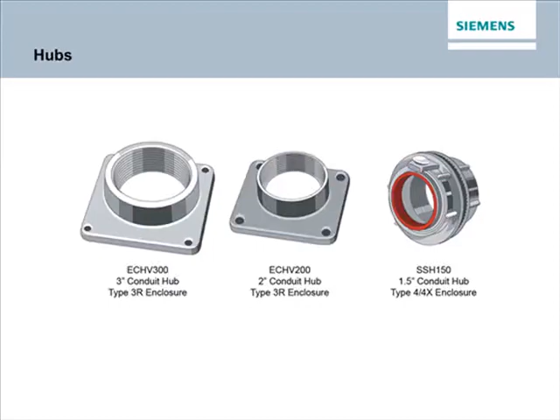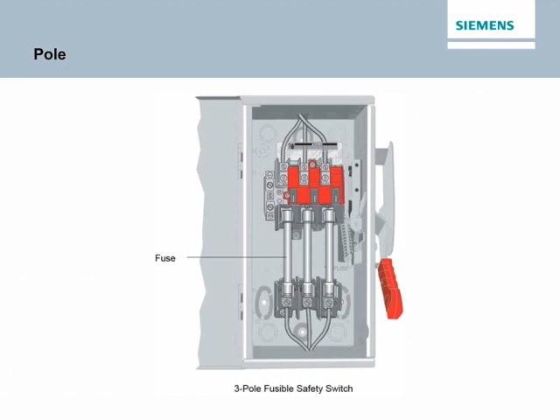The term pole refers to the number of circuits that can pass through a switch at one time. This is the number of circuits that the device can connect and disconnect. The accompanying drawing, for example, shows a 3-pole safety switch. The 3 circuits are mechanically connected so that all 3 of the poles connect and disconnect that line and load simultaneously when the switch is operating. In this example, each pole is fused for overcurrent protection.